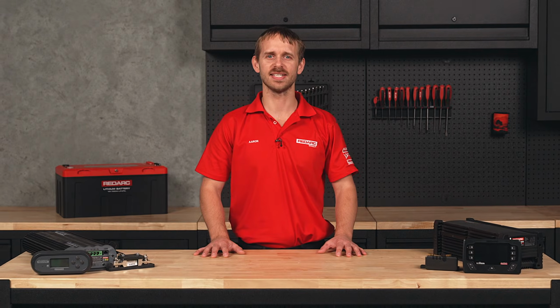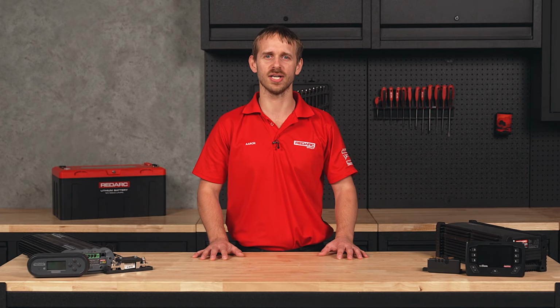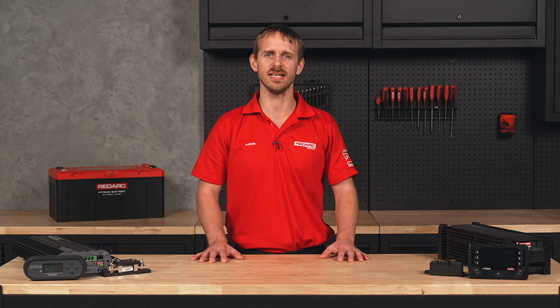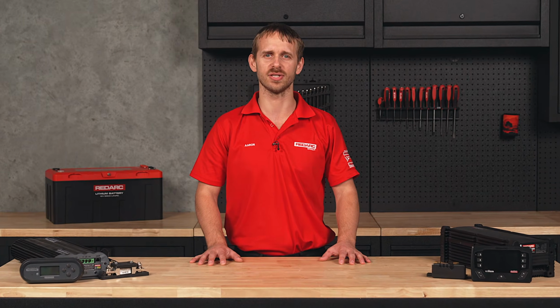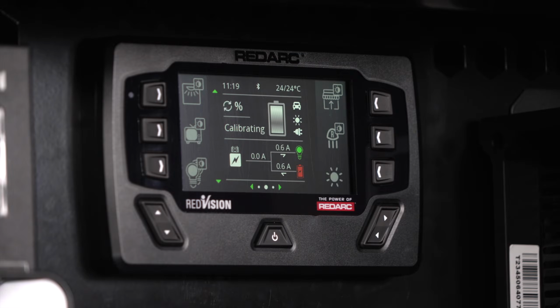Once this information is set, the system needs to fully charge the battery to determine its actual capacity and to display accurate state of charge. Until the battery has received a full charge, the screen will display the word Calibrating.